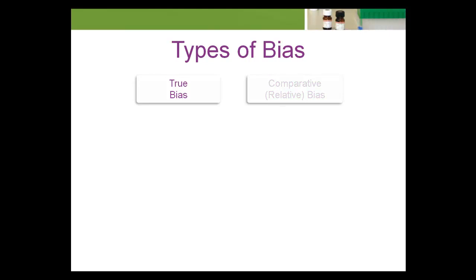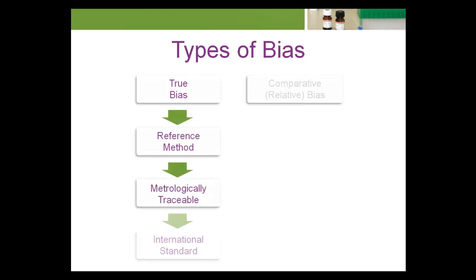True bias is the difference between an observed value and the value for the same analyte derived by a reference method that's metrologically traceable to an international standard. Most control materials do not have such traceability, and those that do are usually very expensive.